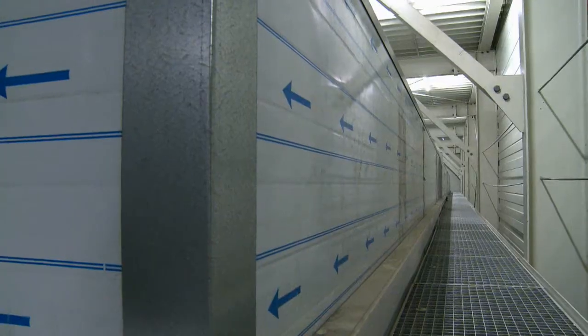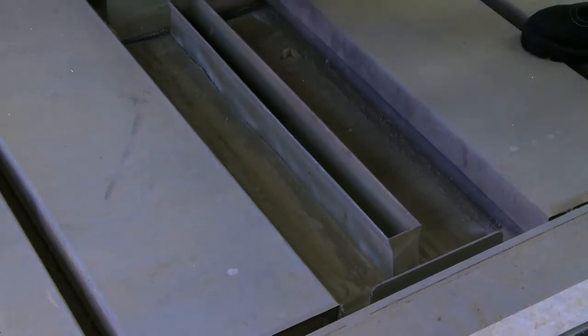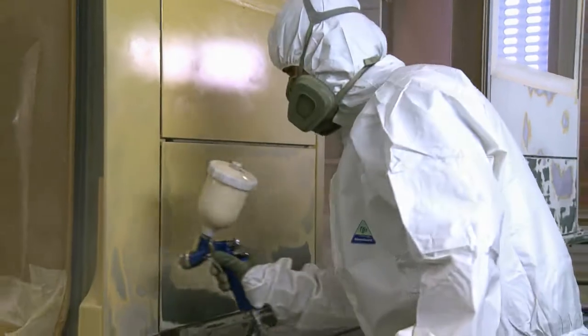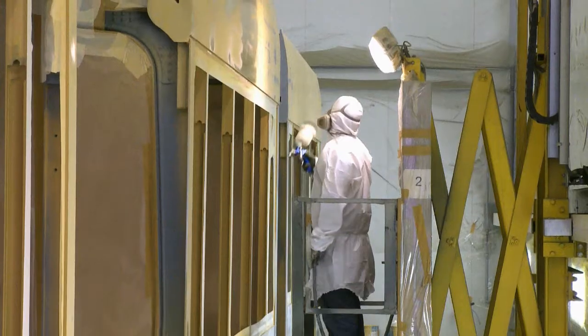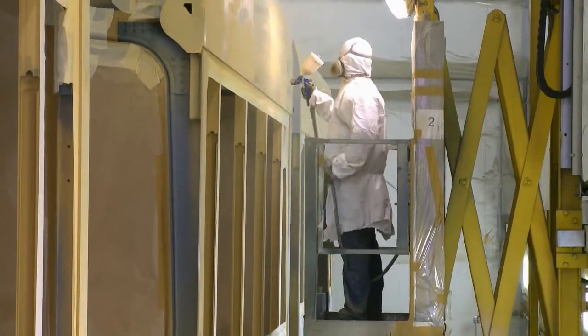Controlling the louvers in the air supply ducts above the cabin and opening the appropriate number of in-floor louvers beneath the impact separators causes the vertical flow of air to entrain the overspray. But because the air flows only where it is actually used, this system achieves energy savings of 70%. The operator recognition system switches on a group of three filter cassettes so that a floating zone of fresh air always accompanies the operator. If the work requires a specific arrangement of zones, these can also be selected manually. This method of operator-dependent sectional ventilation is a patented process.